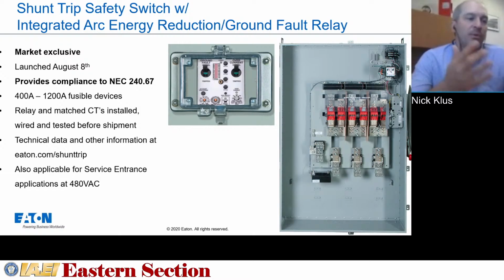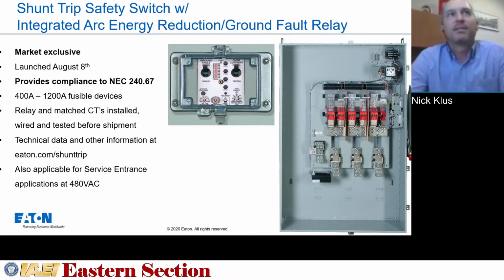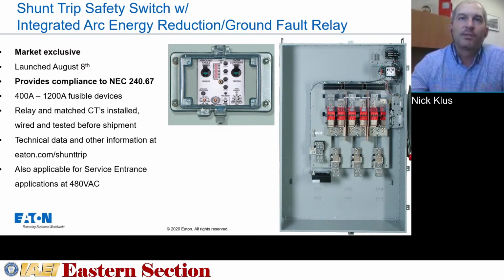So again, when you think about a standard safety switch, now a safety switch with a shunt trip mechanism and also this relay built in, the other key thing to point out, if you look at the picture of the safety switch, is that this is really a fully assembled product designed to tackle 240.67. So you not only get the relay and the shunt trip, but you also get the required current sensors, and all the wiring is factory done to connect to that relay, meeting all UL 98 standards and factory tested here at the plant to ensure that it's operating correctly. So it's really an out of the box solution for this product.